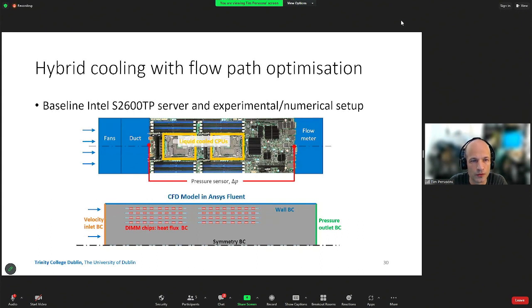So we took a reference server, an Intel server, because we were working with Intel at the time. So this particular server here has chassis fans, and this kind of setup with two CPUs, one after the other. We instrumented this with a delta P sensor and a flow meter, so we could basically do a simulation in CFD and Fluent, and compare our CFD model to the measured delta P and the flow meter results.